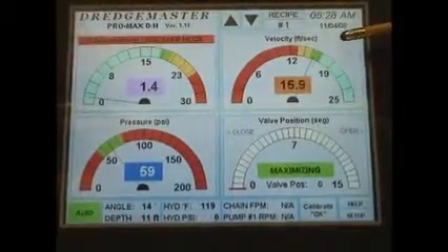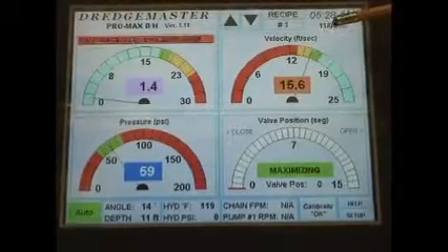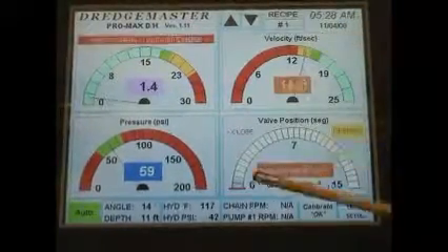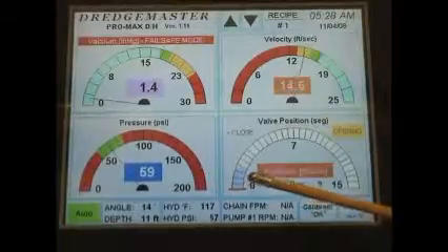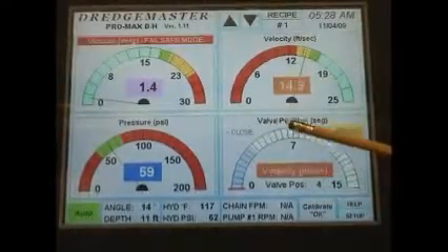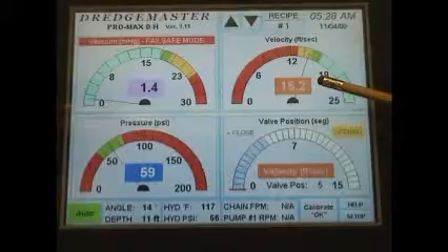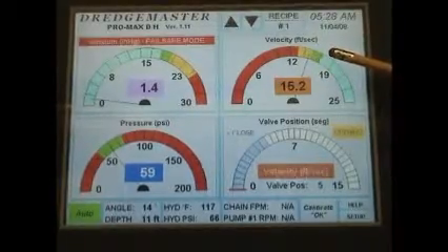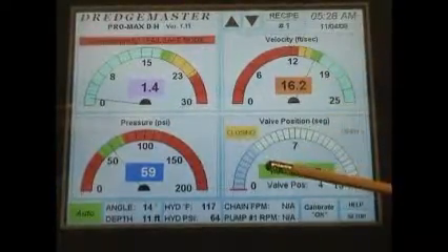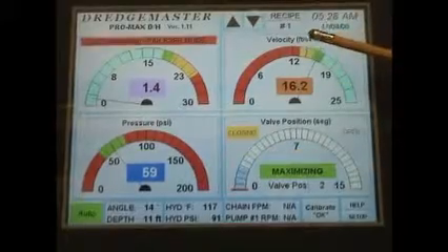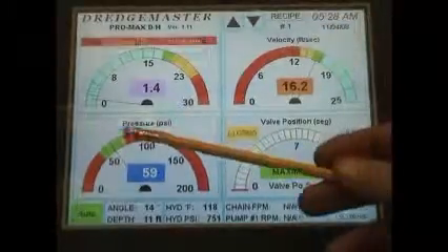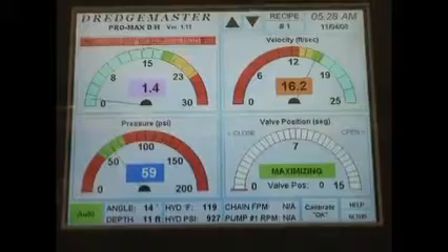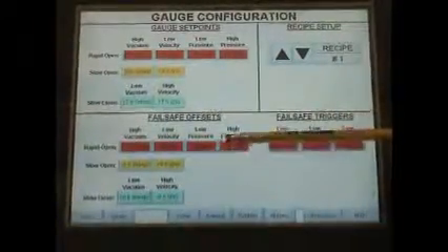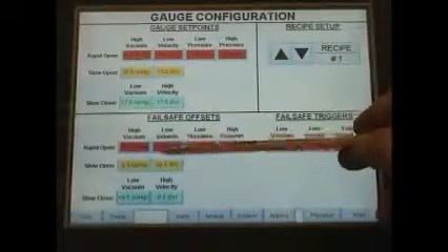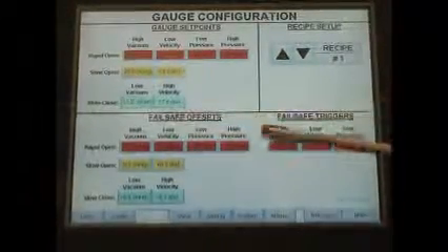So as our velocity starts to drop and gets into the yellow zone, our valve is going to start to open up. As soon as our velocity starts picking up speed into the green zone area, it can start to close itself back down. So our valve continues to now work off of velocity and discharge line pressure. You can change any of these fail-safe offsets by simply touching it and entering in whatever value you want.